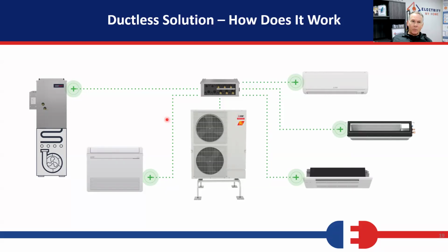So here's the other problem with these. I've got, say, three of these. So we'll just say 5 units. I've got 5 line sets. I've got 2 connections on the ends of each line set, so I've got 4 connections on each line set. That's 20 connections that could possibly leak.